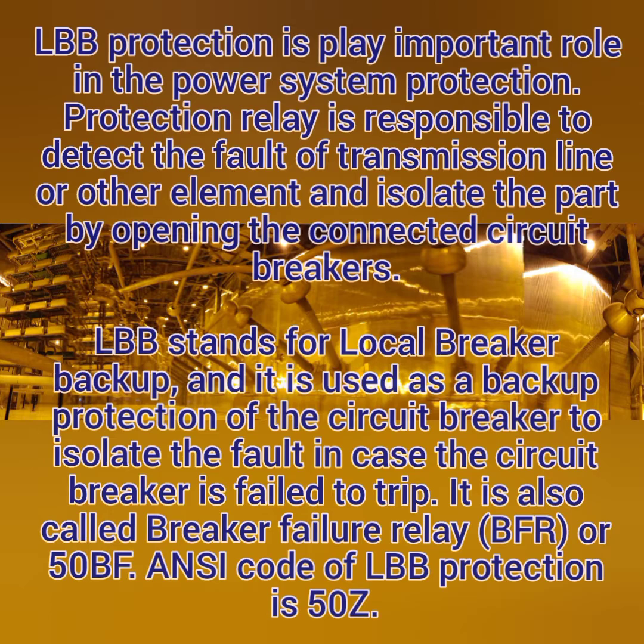But in case the primary protection fails, or the breaker is initiated after the primary protection initiation and still fails to open, due to causes like the coil DC supply failing, the trip coil itself becoming unhealthy or failing to open due to internal faults or damage, or the mechanism getting blocked in your circuit breaker.